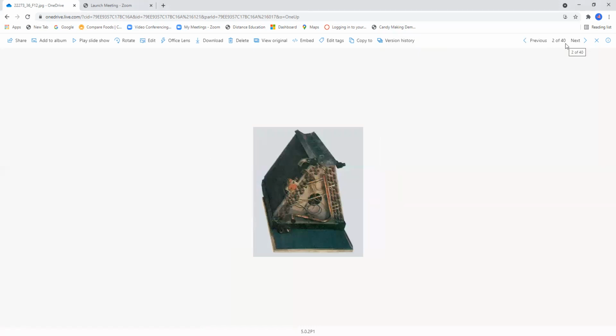Here we have an evaporator coil, which we talked about earlier. This is an A-frame type coil. Notice that the TXV is over here, and you have a distributor that has several circuits. It's a little hard to see without blowing this picture up. And then, of course, here you have your refrigerant connections. One is going to be the suction line. The other one is going to be the liquid line right up here.